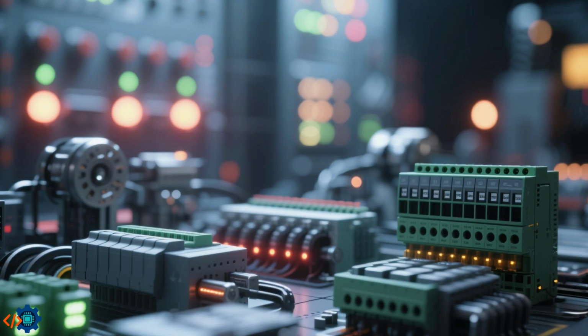When the PLC scans the program, it first reads all the inputs, I, executes the logic in the OB1 block, and then updates the outputs, Q. This process happens thousands of times per second, so the PLC is constantly reading, processing, and writing data. That's why understanding how to use I and Q addresses in your code is essential.